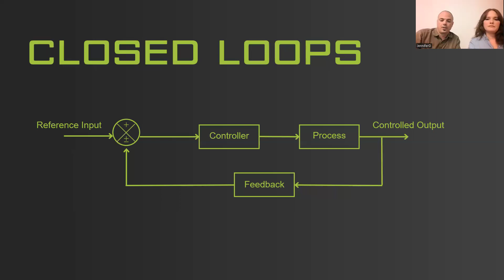So now let's go into a couple of the control loop types, because we can use loops to manipulate various different types of components, and that's going to relate a lot to, for instance, our binary versus analog that we covered earlier. So what if we had a binary function that we are controlling with a loop? Well, we're going to use a binary style of loop. Let's say we have a rooftop unit that has a compressor and all you do is stage it on and stage it off. Well, that's where this is going to come into play.